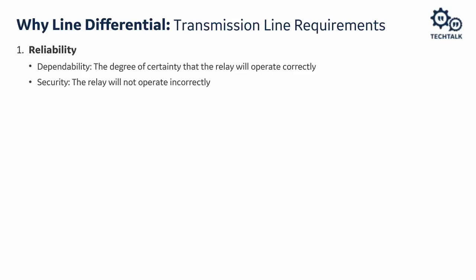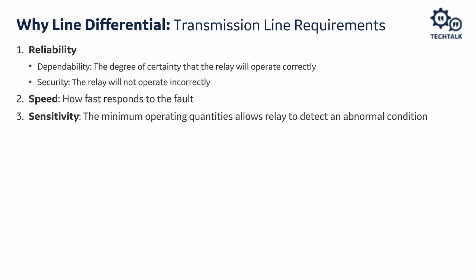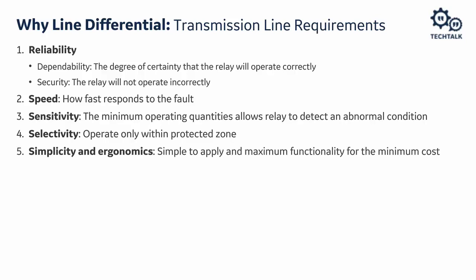Many people ask why we are evaluating line differential instead of distance. Looking at requirements for line protection: first, protection has to be reliable — dependable and secure. Second, we want protection to be fast, clearing faults as quickly as possible. We also need sensitivity — the minimum operating quantity, especially important for high-resistive faults. We want selectivity, operating only within the protection zone. And we want simplicity — maximum functionality for minimum cost.